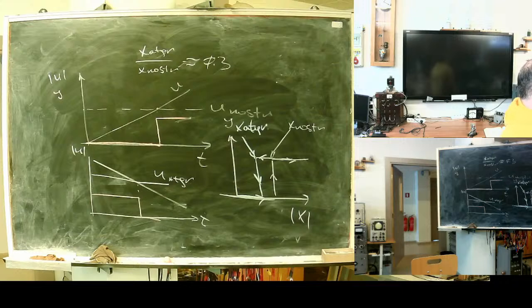Some scholars use this terminology: start is the moment when supply power is applied to the device, when the device is energized. And pickup is the moment when the current, or line or protected object conditions, are outside of normal and we need to operate. I will use mostly start time, but to explain, some scholars use this terminology. The start moment is when power is applied to the relay itself. When you plug in your phone, it's a start moment. Your phone sees your face and starts face recognition, it's a pickup. And it's decided that you can go in, it's a trip.